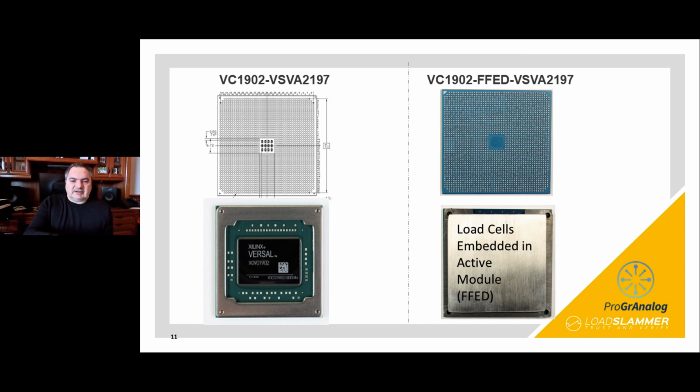The other thing is, there's a lot more functionality. We're testing the rails with the load cells, and they're closer to the socket, or in this case, the LGA pad or the land pad of the DUT that you've developed. So our di/dt can be much faster, so you've got much greater possibility. You can stress test your di/dts, your excursions, more rigorously with this solution, if you will.